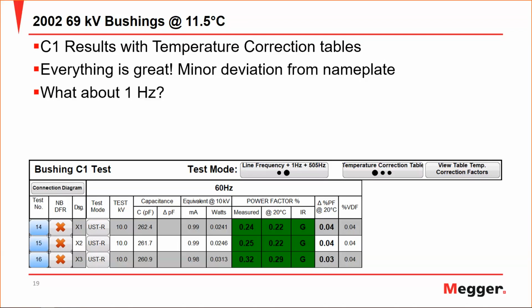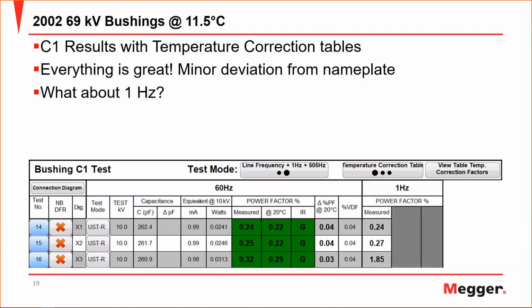But if we look at 1 Hertz, we can see that the X3 bushing here is showing quite a bit of a difference from its sister bushings. And again, at this point, we don't even need ITC, but we will go through that. But when you are looking at a sister asset that was built in the same year, that is operating at the same voltage, that was built by the same manufacturer, presumably out of the same batch, and it's been running in the same environmental condition as the other sister assets or other bushings, if a value starts to change, then you can be pretty confident that there is a change occurring with that single bushing.